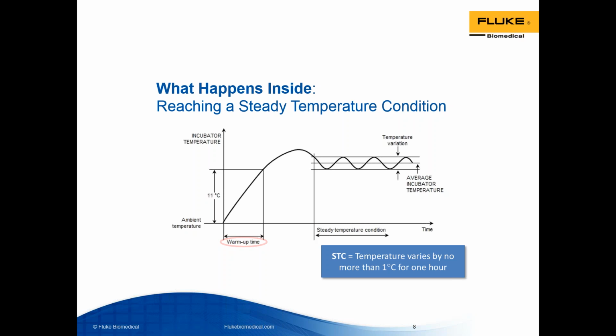So after the incubator goes through its warm-up time and reaches its set point, the temperature will then overshoot and then undershoot and then oscillate in small temperature variations, resulting in an average temperature of the incubator. So when we think about the acceptable ranges that an incubator overshoots and then undershoots, we have to remember just how fragile the infants are to even minute changes in temperature. According to the standards, and what I'm talking about is the IEC 60601-2-19 standard for incubator testing, where this diagram was actually adapted from, the overshoot shouldn't be more than 2 degrees Celsius.